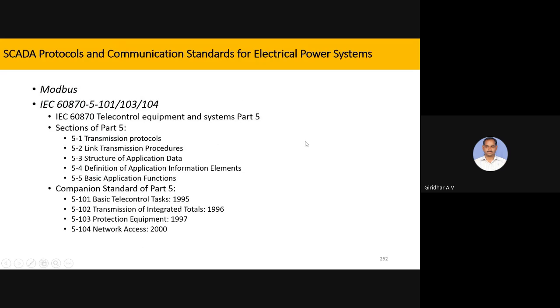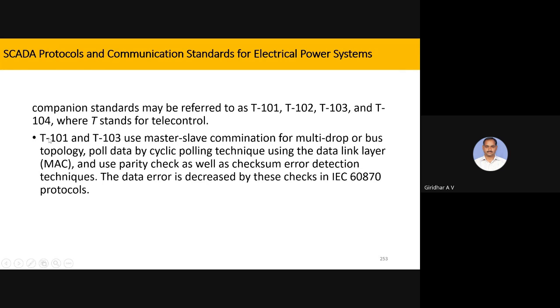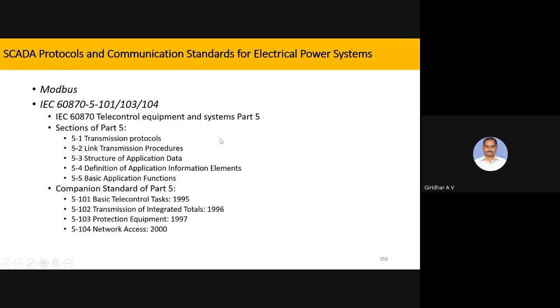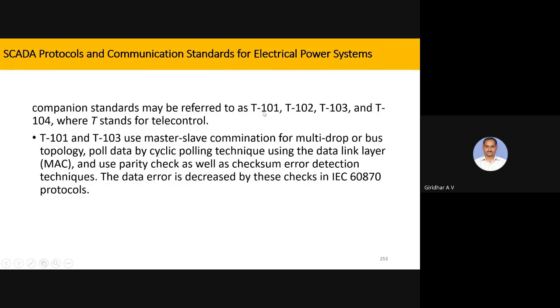So there are different protocols we are using: Modbus type of communication protocols, IEC 60870, telecontrol equipment type of protocols. You can even see a companion standard in that communication, IEC 60870. So T101, T102, T103. This telecontrol, suppose 101, 103, is master-slave communication, with a particular bus topology, cyclic polling techniques, and different things it does.